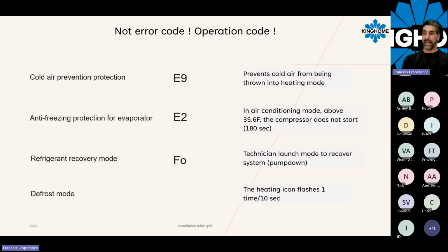So meaning that case we are in cooling mode, and for example, the filter is completely blocked and the head is sensing less than 32 degree Fahrenheit. Well, this E2 will appear telling the systems that we need to stop the compressor for at least 3 minutes, and also we will wait till the sensor located on the evaporator will read 35.6 before we can go in cooling mode again. So during that time, maybe you will see an E2. So this is a protection of the evaporator.